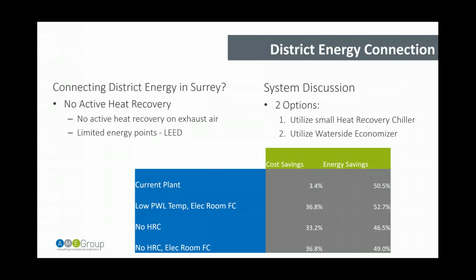And so looking at two options, one was utilizing a small heat recovery chiller for just the simultaneous heating and cooling loads, and the other was utilizing a water side economizer on the chilled water side. And so as you can see on the chart there, when we look at the bottom two, the low processed water leaving temperature and the no heat recovery chiller with electric room fan coils, the energy cost savings was the exact same. And those were the two strategies that we were really looking at.